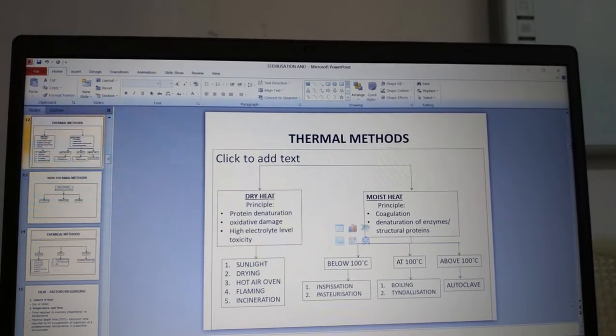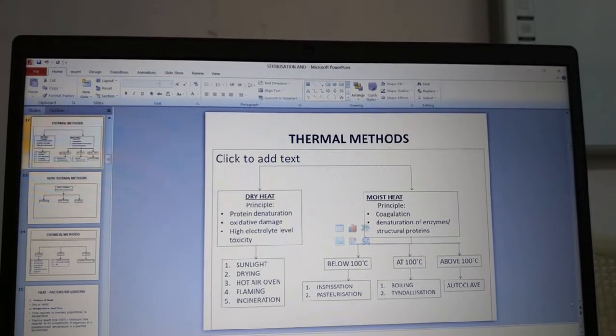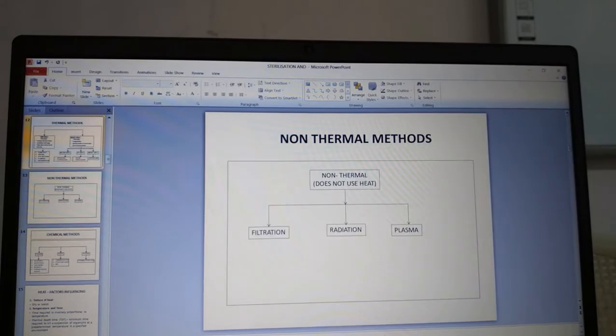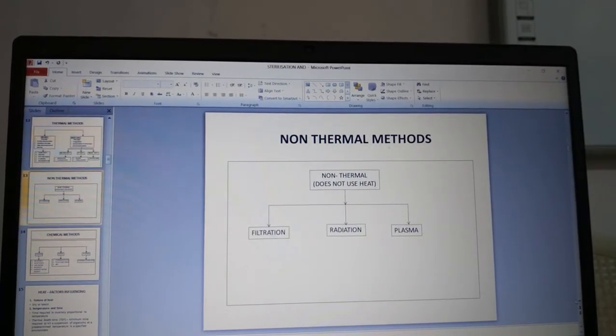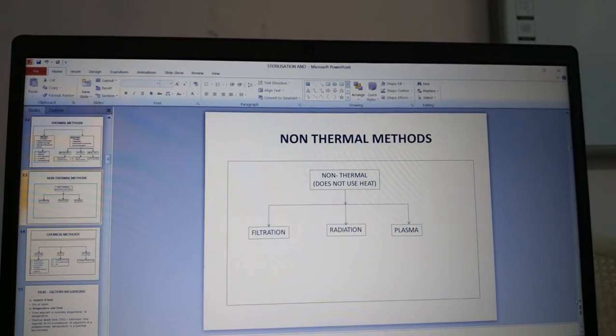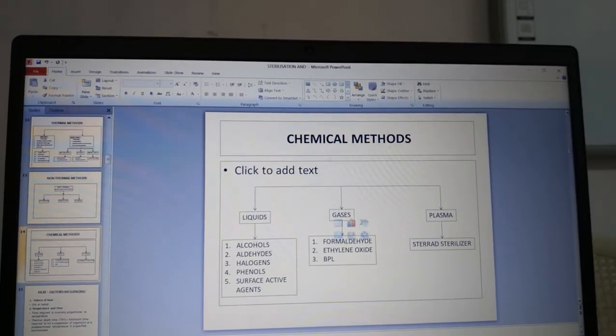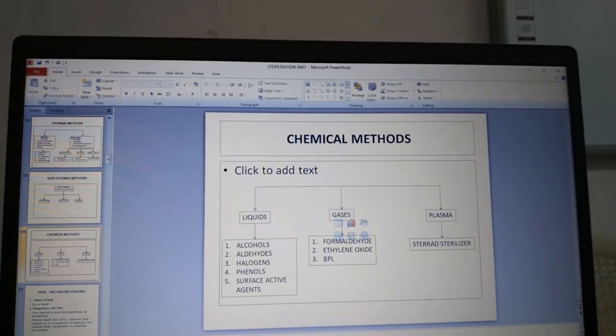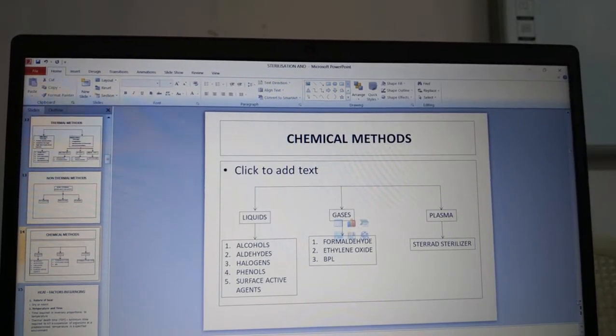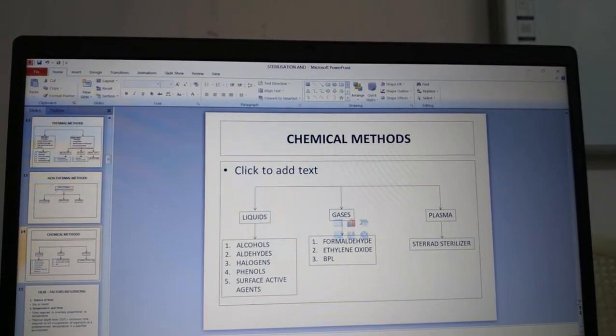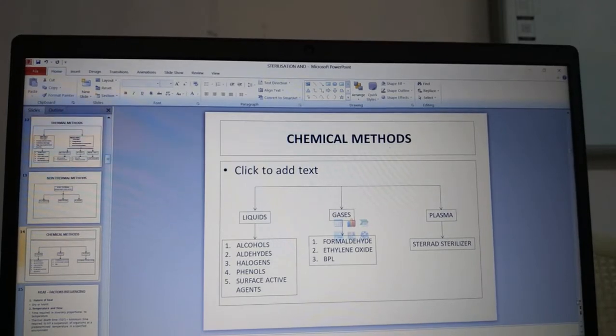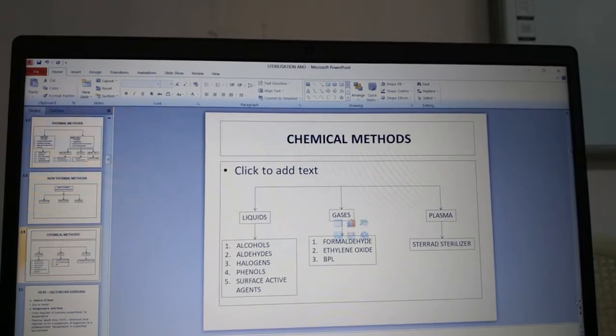Non-thermal methods do not use heat — we have filtration, radiation and plasma sterilization. Chemical methods include liquids, gases and plasma. Under liquids: alcohols, aldehydes, halogens, phenols and surface active agents. Gases include formaldehyde, ethylene oxide and BPL (beta-propiolactone). Under plasma we have the Sterrad sterilizer.